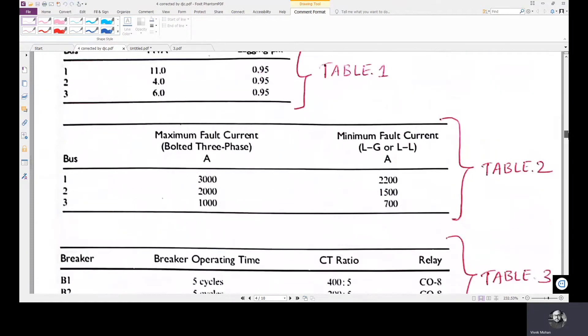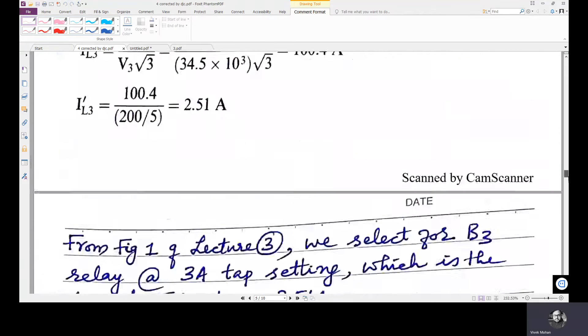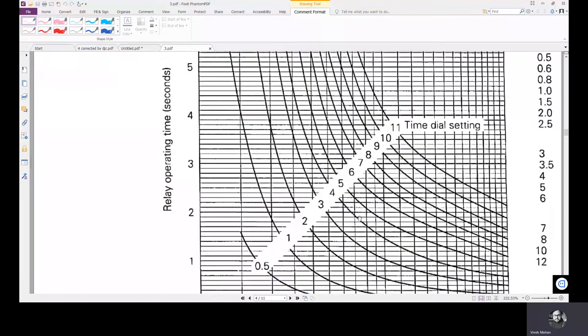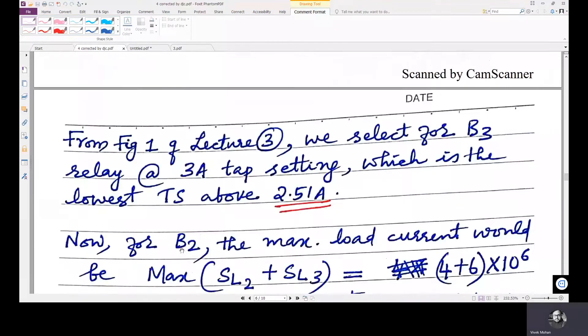The CT ratio for B3 is 200:5, giving a secondary CT current of 2.51 amps. Since we do not want the relay to act at this normal operating current, we select the lowest current tap setting above 2.51 amps from the Westinghouse CO8 relay characteristics, which is 3 amperes. So, a 3 ampere current tap setting is selected for the B3 relay.